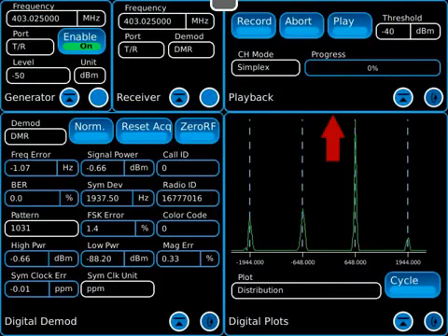The 8800 performs digital voice quality tests by allowing the operator to record the audio data from the radio. The audio data is then played back to the radio to test voice quality. In this way, the operator does not have to rely upon the test set having the particular vocoder the radio uses. Recorded audio can be stored and used at a later time.